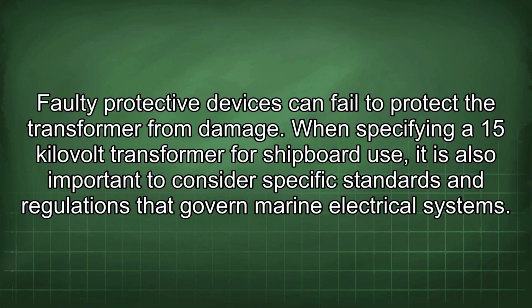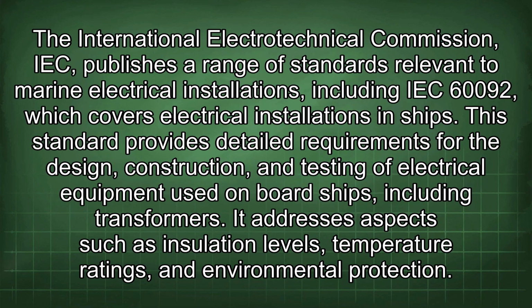When specifying a 15 kV transformer for shipboard use, it is also important to consider specific standards and regulations that govern marine electrical systems. The International Electrotechnical Commission (IEC) publishes a range of standards relevant to marine electrical installations, including IEC 60092, which covers electrical installations in ships. This standard provides detailed requirements for the design, construction, and testing of electrical equipment used on board ships, including transformers. It addresses aspects such as insulation levels, temperature ratings, and environmental protection.